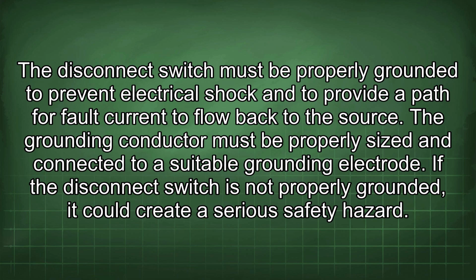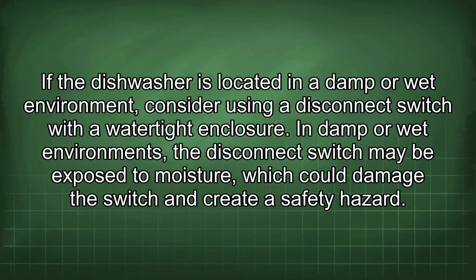The grounding conductor must be properly sized and connected to a suitable grounding electrode. If the disconnect switch is not properly grounded, it could create a serious safety hazard. If the dishwasher is located in a damp or wet environment, consider using a disconnect switch with a watertight enclosure.